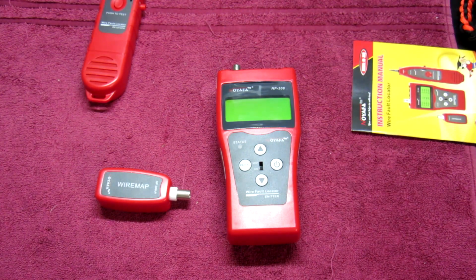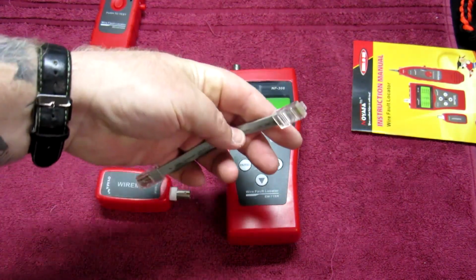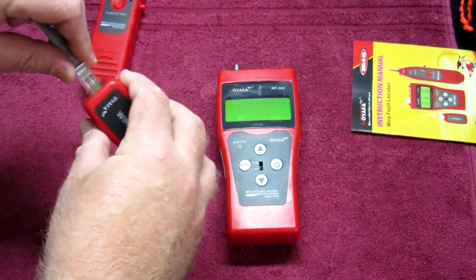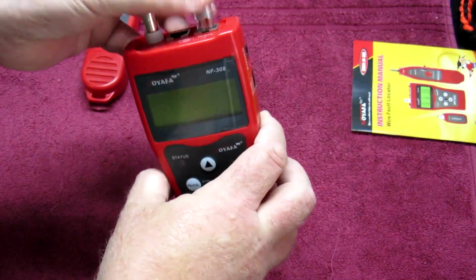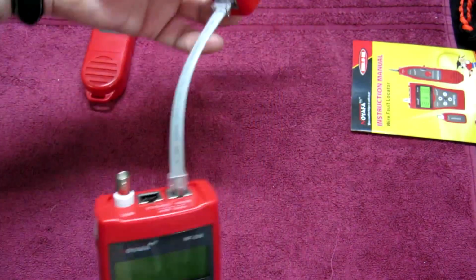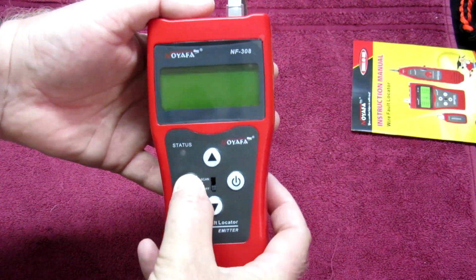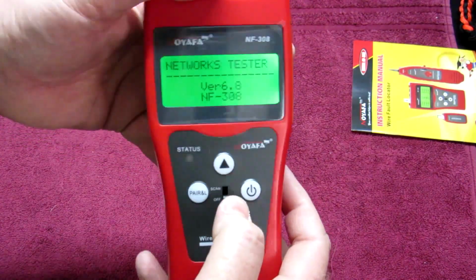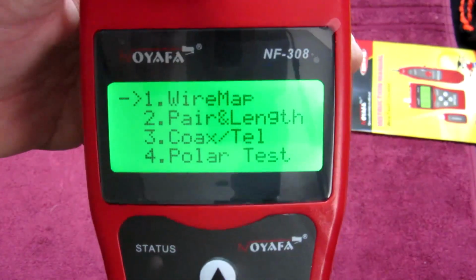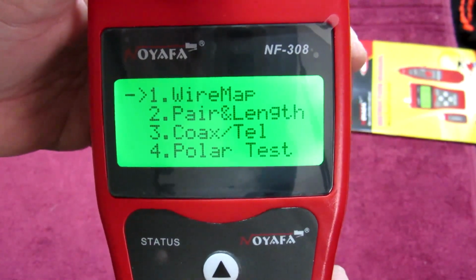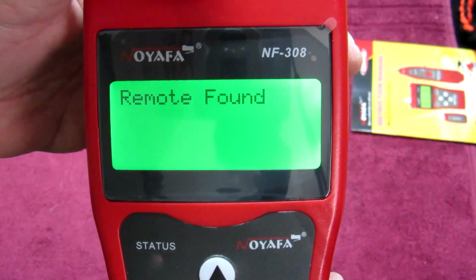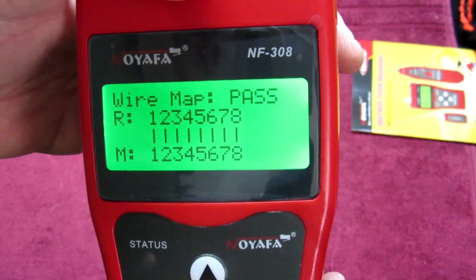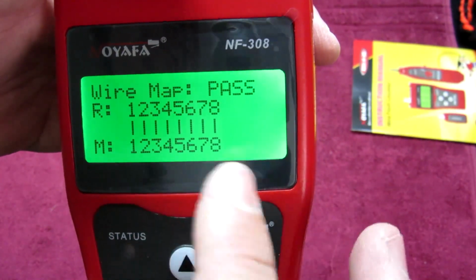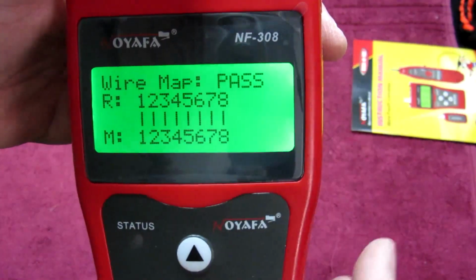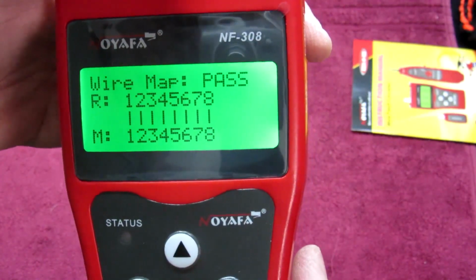Say for example you have a Cat5 cable. Obviously this isn't a full length, but a Cat5 cable you want to test. You basically connect this onto the Cat5 cable between these two devices. You switch it on, and as you can see, it's got a nice LCD display, like so. Then you select wire map, and it'll test all the cables, and there you have it. As you can see, main unit, this unit, and the remote unit, all cables are connected. Map pass. Happy days. So there you go.